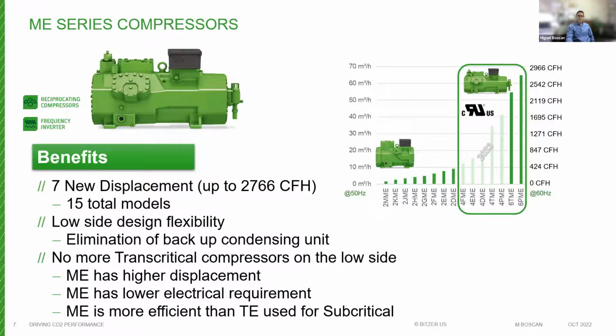So you will be able to design the low side with fewer compressors, optimized for that application. And it also gives the opportunity to consider other options, like eliminating the backup condensing units on the low side, because these compressors can withstand higher standstills. The 2-cylinder series has been released for quite a while. Coming up in 2023 will be the 4- and 6-cylinder versions.